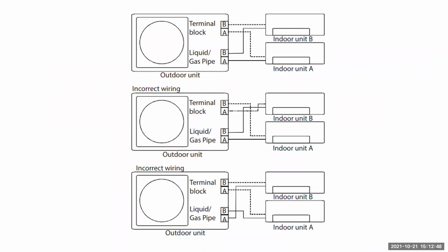And the reason that we don't want you to do that is because you hit that button to solve your issue. But if you had to change a board, then all of a sudden you're going to have this issue and you're going to be questioning what's going on. Obviously you want your refrigerant lines to go from A to A and B to B, and also unit A to B.